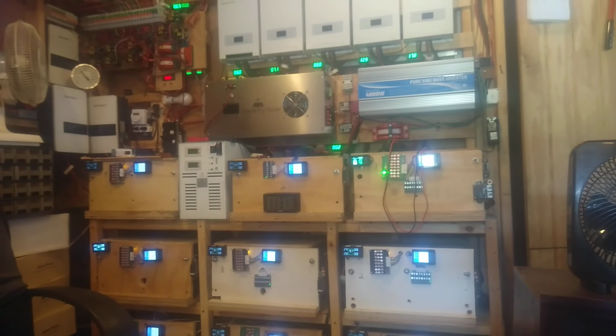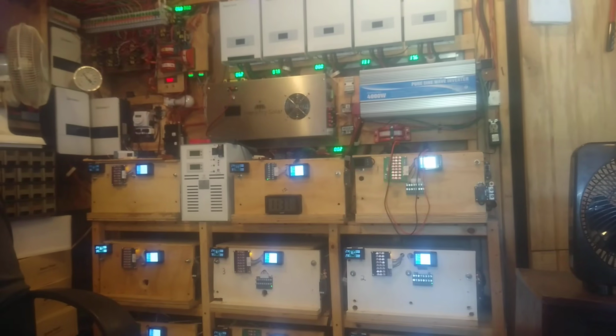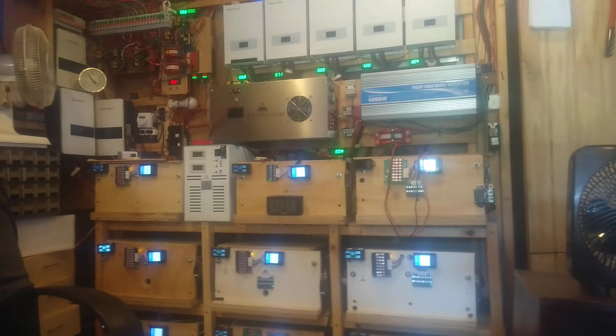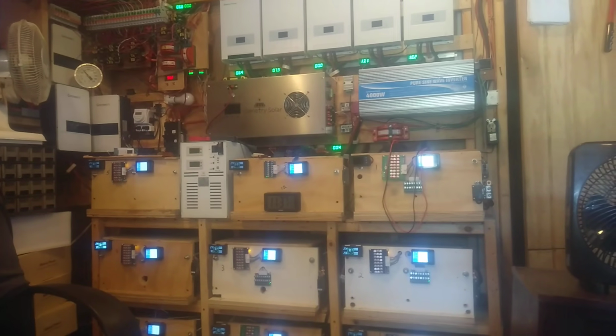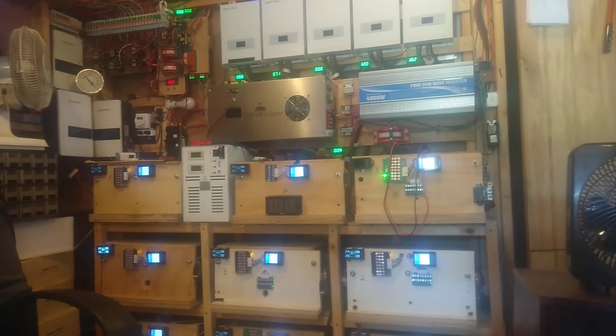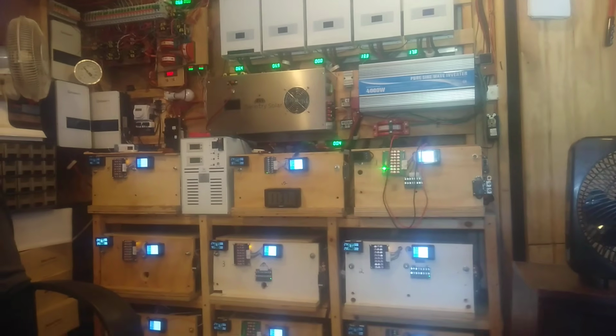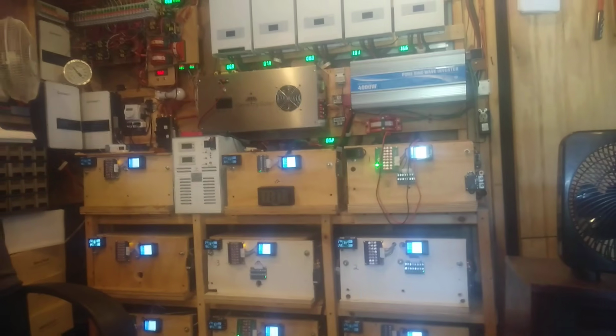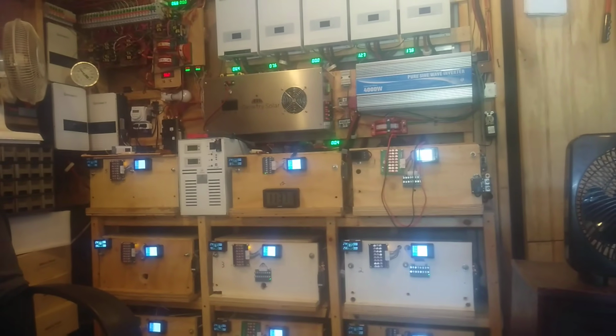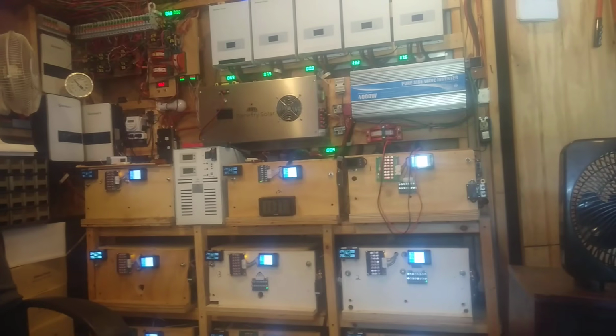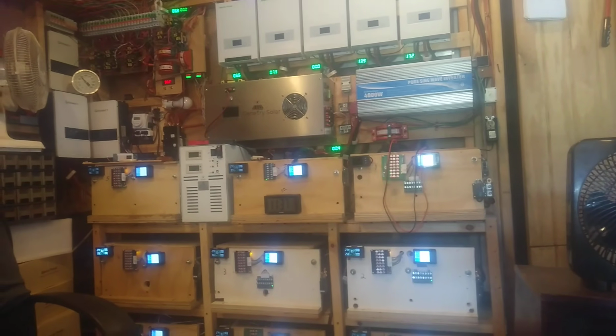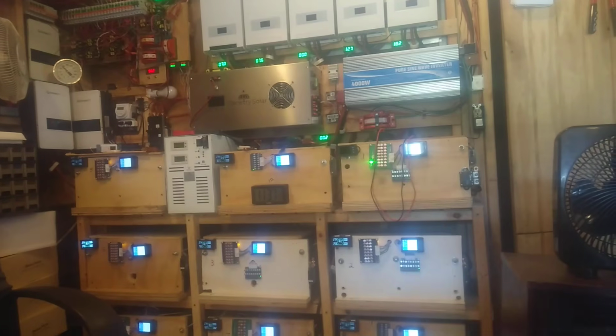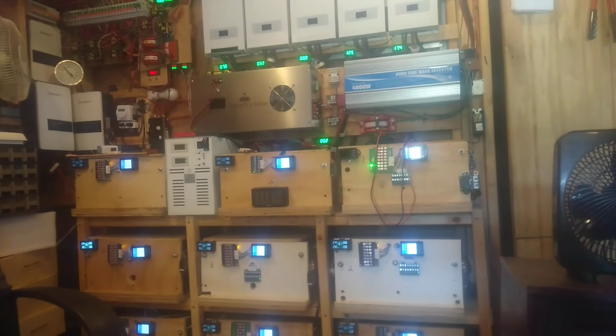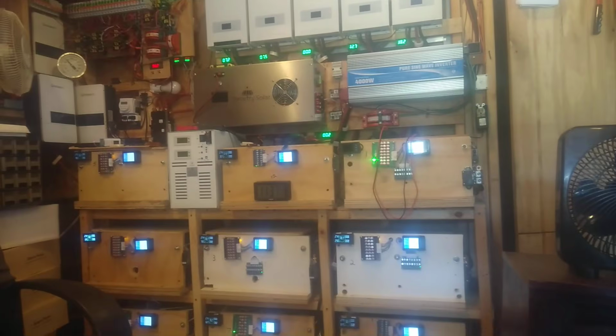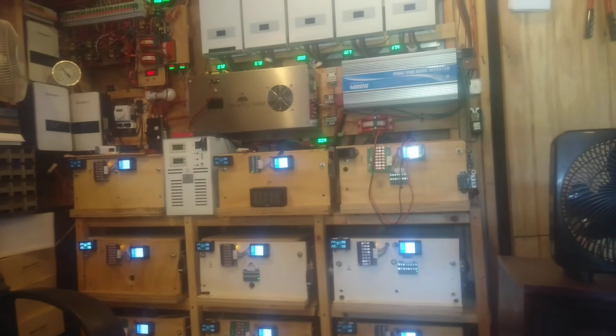It allowed the cell voltage to get above 3.65, which caused the sacks inside the cell to expand and probably rupture and broke the seal on the cells, allowing the gases on the inside to escape. What I didn't know at the time, until just recently, is that those gases contain hydrogen. Hydrogen gas is probably one of the most explosive gases known to man. So if you've got hydrogen leaking out of your cells into a well-sealed building, with all the electronics running in there, it's not going to take long for a spark to happen and blow that building to pieces.